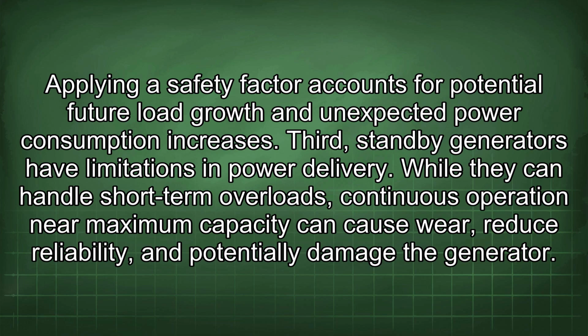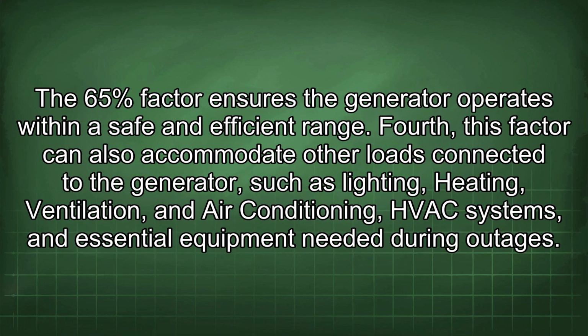Third, standby generators have limitations in power delivery. While they can handle short-term overloads, continuous operation near maximum capacity can cause wear, reduce reliability, and potentially damage the generator. The 65% factor ensures the generator operates within a safe and efficient range. Fourth, this factor can also accommodate other loads connected to the generator, such as lighting, heating, ventilation, and air conditioning, HVAC systems, and essential equipment needed during outages.